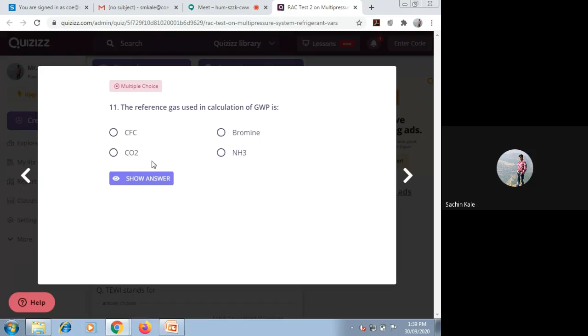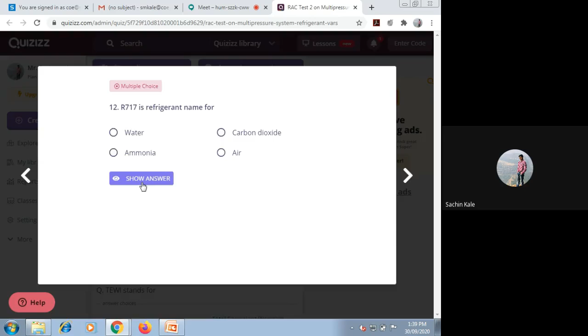That global warming potential will be mainly caused because of the carbon dioxide, and the reference gas in the calculation of GWP will be considered as carbon dioxide. Then next one, R717 is a refrigerant name for. So what is the answer? 717, as this is the 700 series, that's why inorganic compound. So 700 plus molecular weight. So 17 is the molecular weight for ammonia. That's why R717 will be the refrigerant called as ammonia.